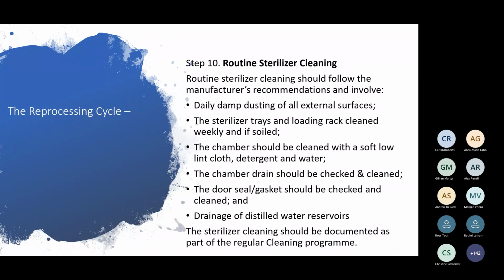So we also need to clean our sterilizer. The sterilizer works hard for us, so make sure you look after the sterilizer as well. So your routine cleaning should be following the manufacturer's instructions as well, but should also involve damp dusting of all the external surfaces of the machine. If you look at your machines, you'll often see there's like little fish gills or something on the side of them. They're actually air vents. So please check those air vents. If you see that they're full of fluff and lint and things, clean them, get rid of that stuff because that's where your air is actually coming into the machine to help your machine work. If those gills get clogged, then that can cause your machine to stop working as well.